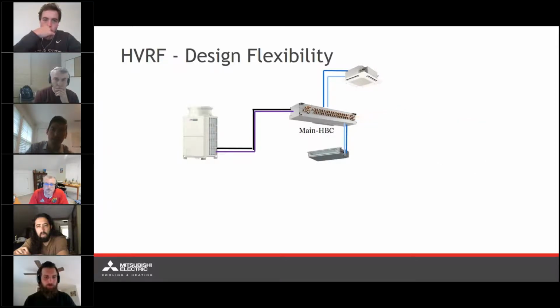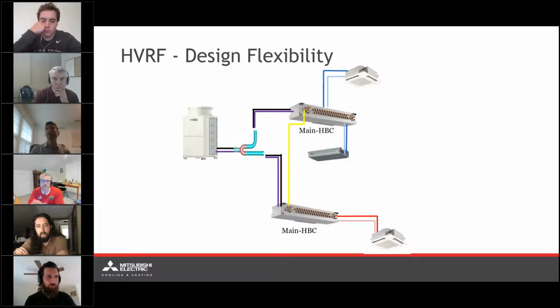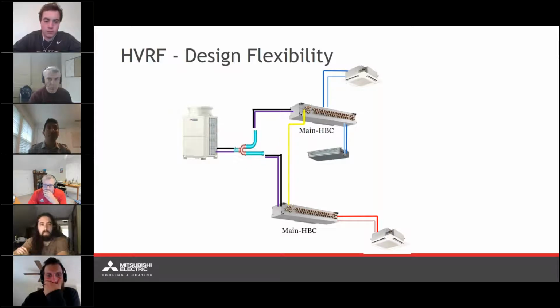Now here's where the really interesting thing comes in. What is new with the hybrid VRF system is the ability to have a second main hybrid main BC controller. So forgive me if I'm saying hybrid BC or HBC or BC controller. Ultimately, I'm talking about the same thing here. So the difference between a secondary main HBC and a sub BC controller, that's just like an expansion, is that the main BC essentially operates as its own individual datum point when we're talking about line lengths for a system.